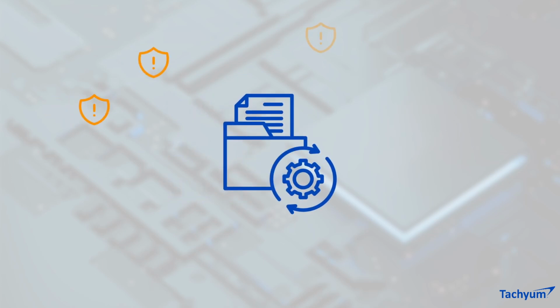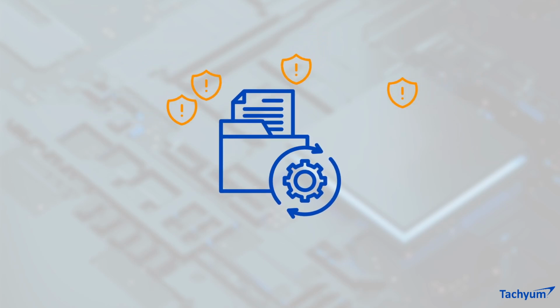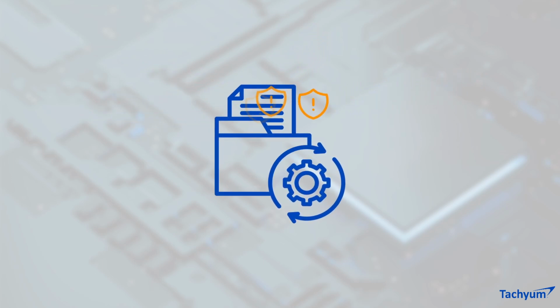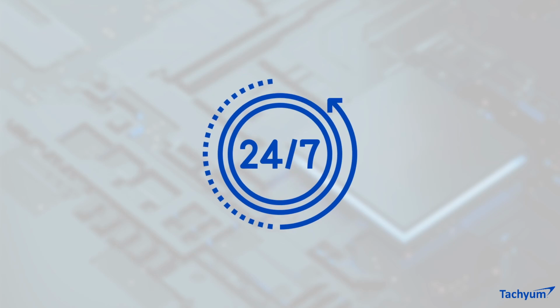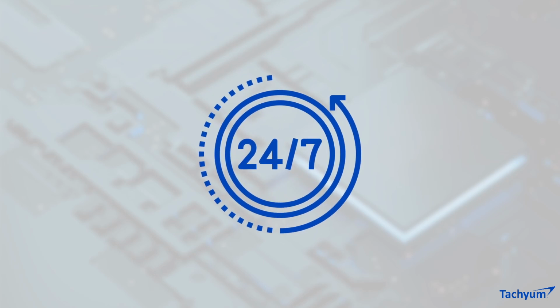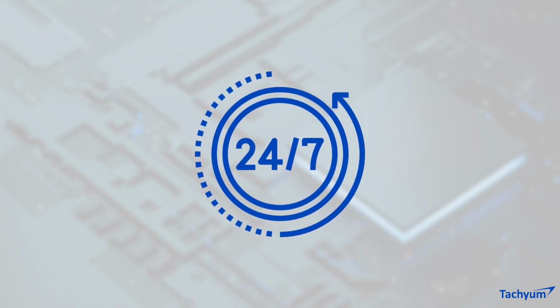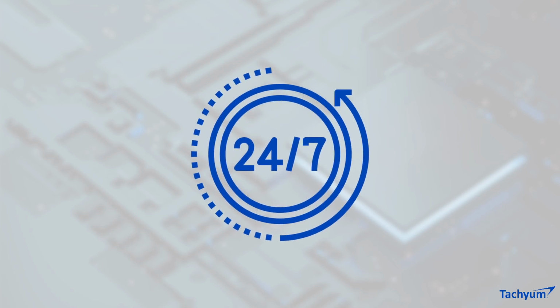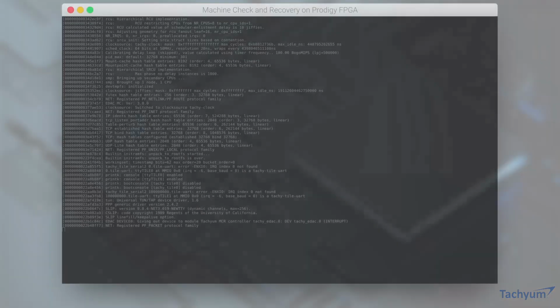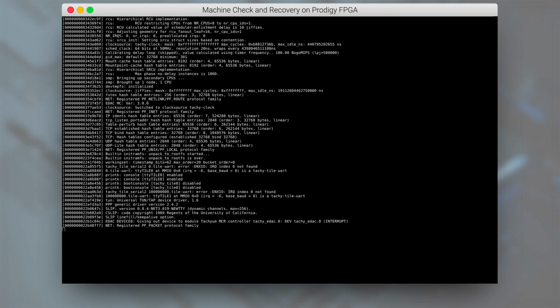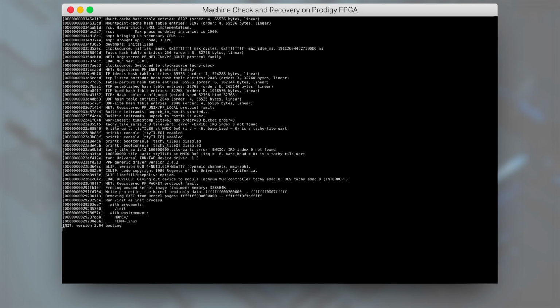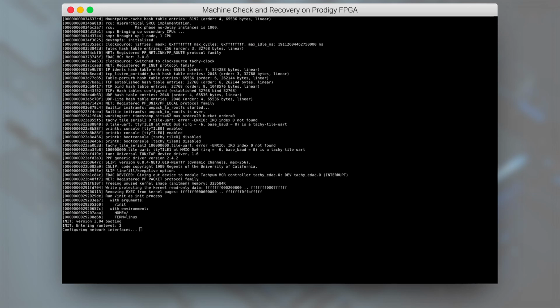Logging the amount and rate of correctable errors with the EDAC facilities of the OS provide plenty of information to proactive administration teams and allows for preventive maintenance to keep data center uptime incident-free for as long as possible. In our demo, we're demonstrating that Prodigy can correct memory errors caused by our error injection module, report the event to the OS, and that the EDAC subsystem reacts and logs those events.